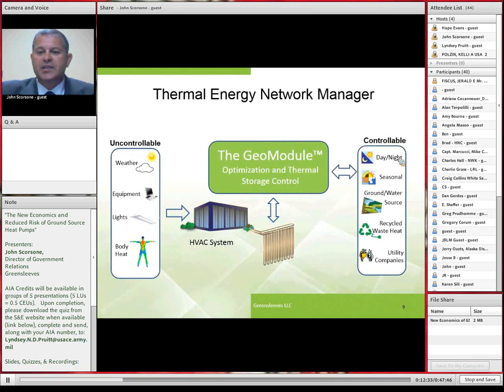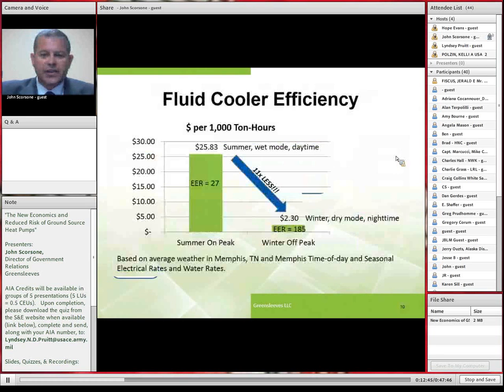So let's take a look at what this means for efficiency. If a designer uses a traditional hybrid ground source heat pump system, it will run its cooling tower or fluid cooler when the loop field temperature gets hot. In the Nashville area, 1,000 ton-hours of fluid cooler run will cost about $25. And that's with a really good system that has an EER, energy efficiency ratio, of 27. But if we store this heat and then later choose when we get rid of it in the winter, our EER can soar to 185, costing only $2.30 per 1,000 ton-hours. This is an amazing difference, and that's the value of intelligent predictive systems that control when and where you get rid of the excess heat.